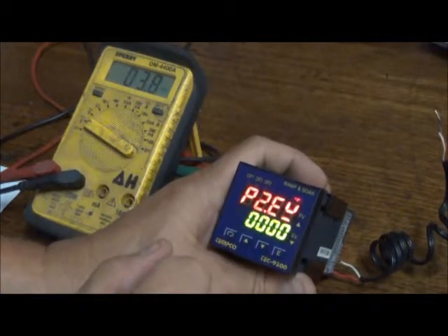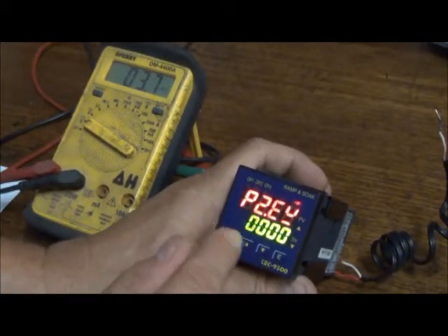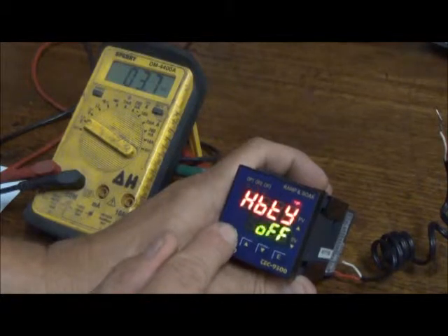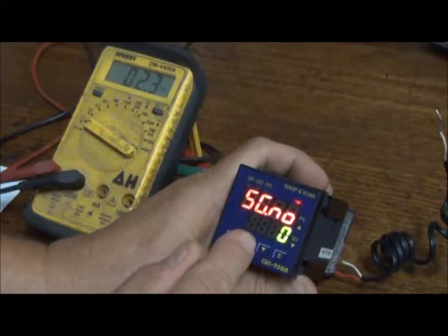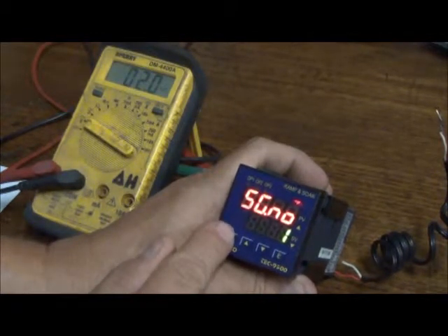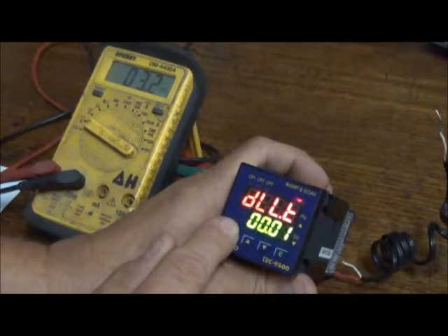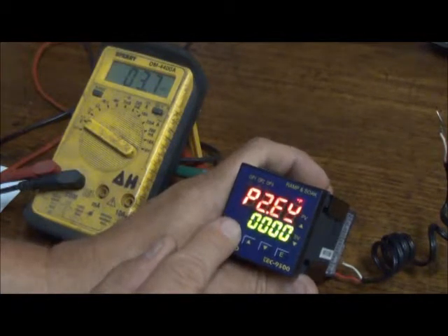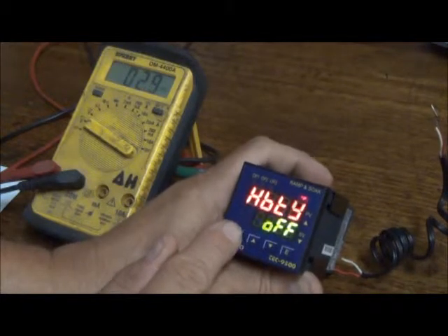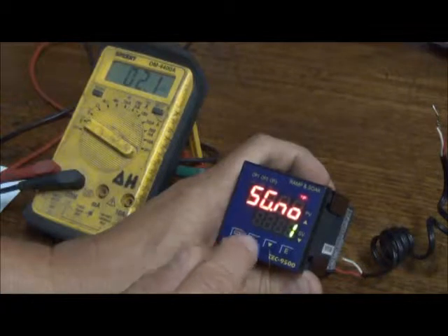All right. So this is the parameter for which tuning constants you want to use. Just leave that at 0. Hold back is off. And now we're going to segment number 1. We just did 0. This is dwell, and we got a dwell time of 1 minute. These PID constants at 0. Leave that off. Hold back, no hold back.